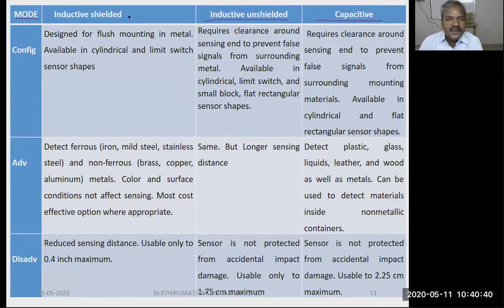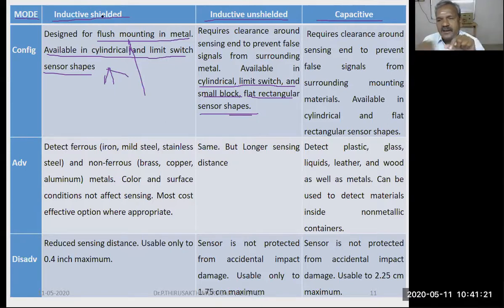The inductive proximity sensor with the shielded configuration is designed for flush mounting in metal, and is available in cylindrical and limit switch shapes. The unshielded inductive is the same, but is also available in cylindrical, limit switch, small block and flat rectangular shapes. In the shielded type, it is safe if any object hits it, because it is shielded, whereas the unshielded type is easily damaged by the object. The capacitive requires clearance around the sensor, to avoid false signals from the surrounding mounting materials. It is also available in cylindrical and flat rectangular shapes.